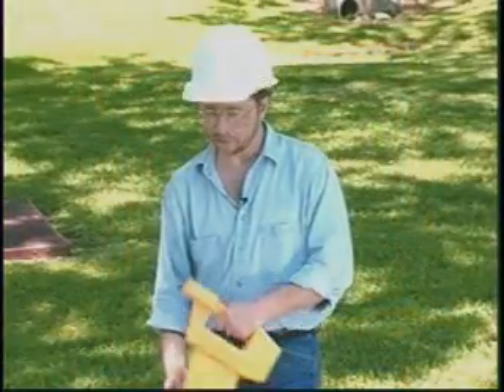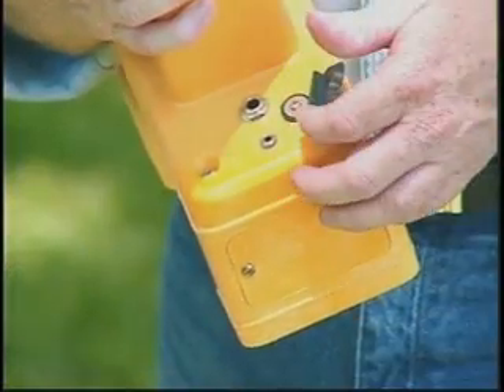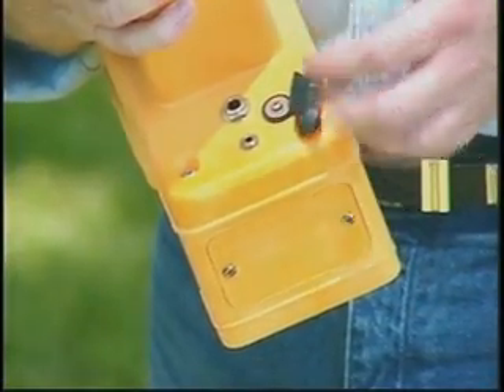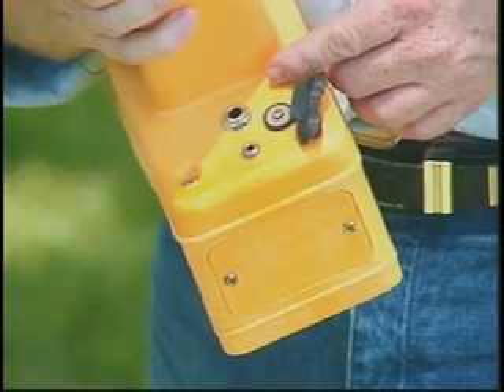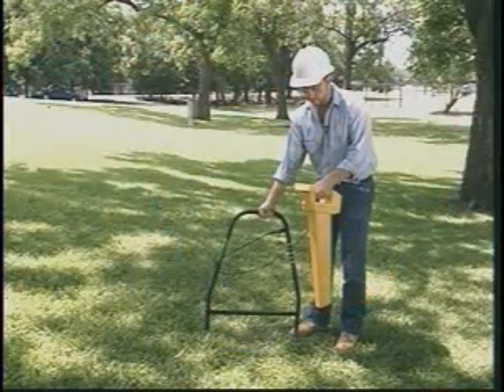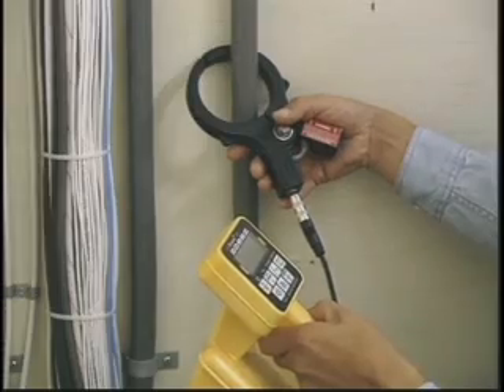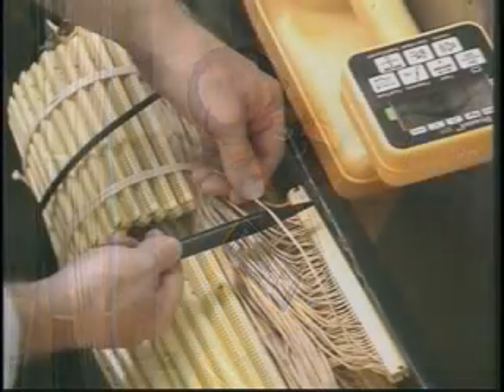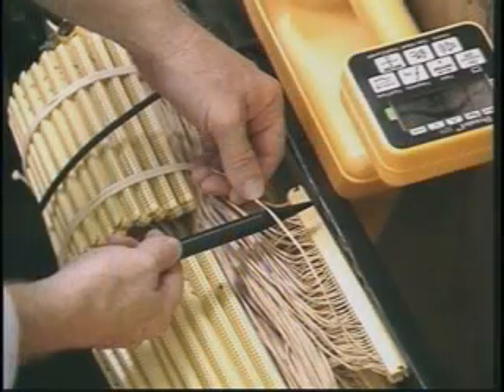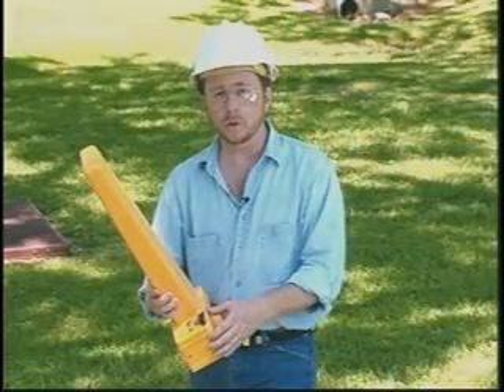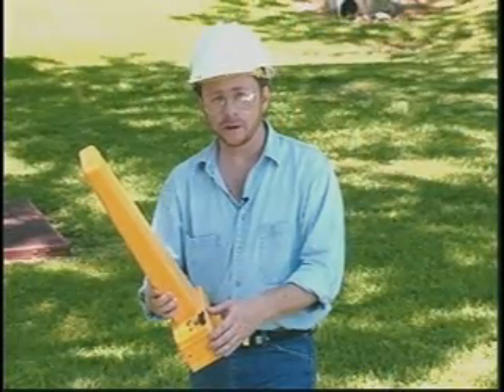On the bottom of the receiver are two jacks. The smaller jack is for headphones. The larger jack is for accessories, such as the earth contact frame for finding sheath faults, the dynacoupler for cable identification, and the tone probe for pair identification. A standard toning coil for aerial fault locating can also be used.